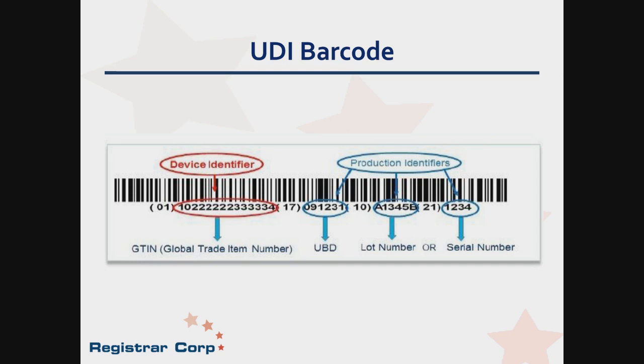So the first part, the red part, is also information that FDA requires you to submit into the global UDI database. The blue part, the production identifier, is not going into that database. FDA has only checkboxes. FDA is only interested in what information you are using on that part of the barcode. So there's a checkbox for a lot or a batch number or for an expiration date, and you just say yes or no. The actual blue part, production identifier information, is stored at your facility in case of an inspection.